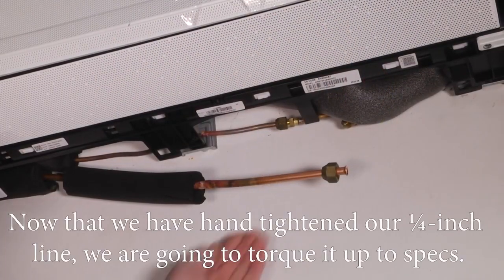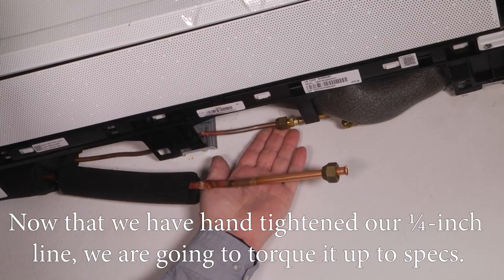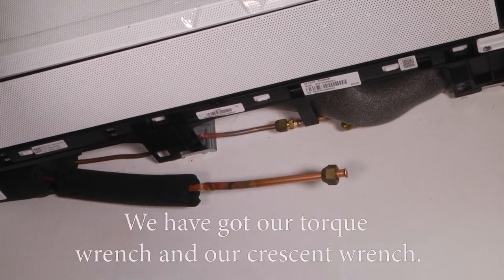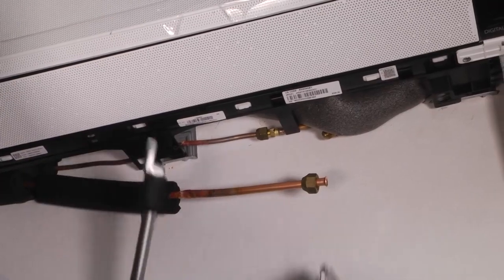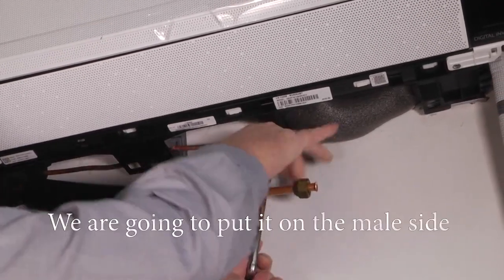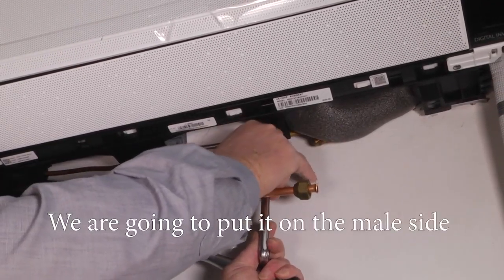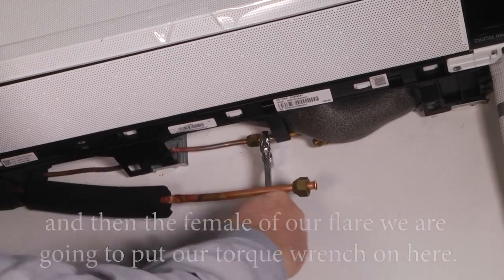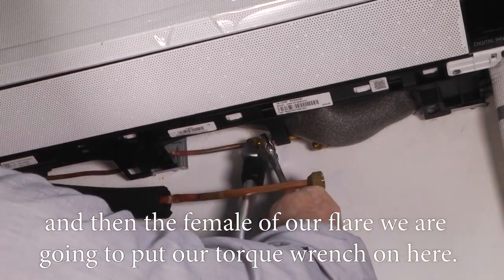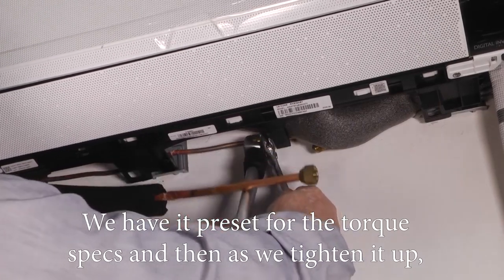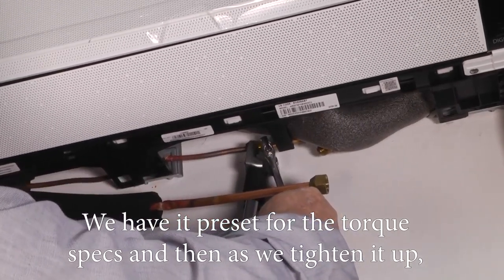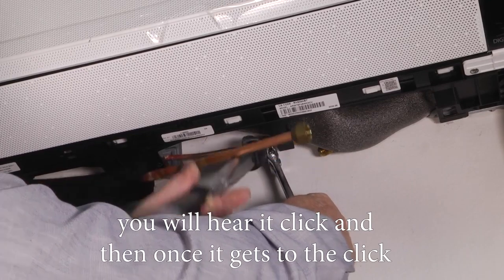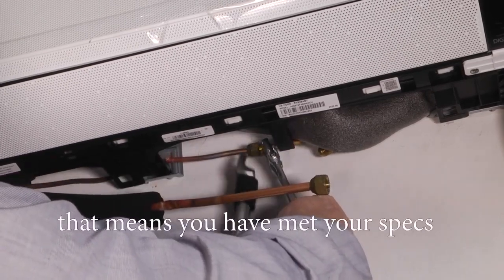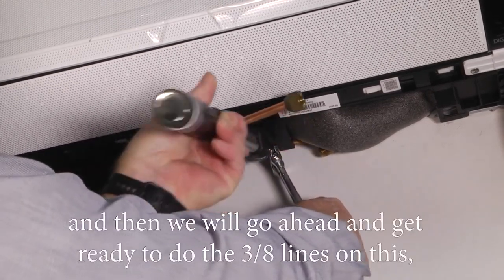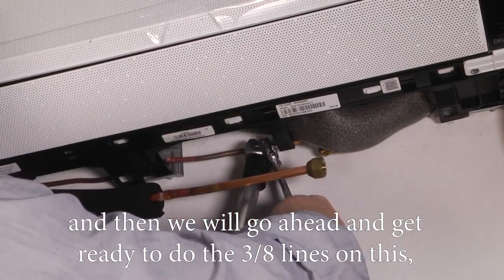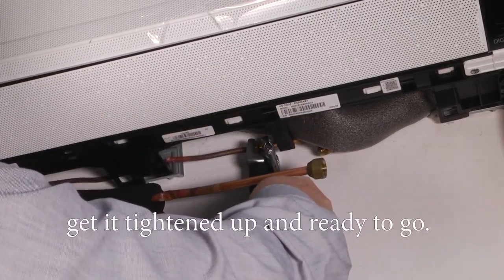All right, now that we've hand tightened our 1/4 inch line, we're going to torque it up to specs. We've got our torque wrench and our crescent wrench. We're going to put the crescent wrench on the male side, and on the female side of our flare, we're going to put our torque wrench. We have it preset for the torque specs. And as we tighten it up, you'll hear it click. Once it clicks, that means you've met your specs. And then we'll go ahead and get ready to do the 3/8 lines on this. Get it tightened up and ready to go.